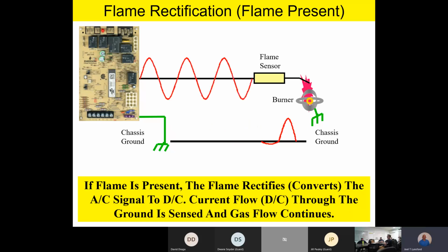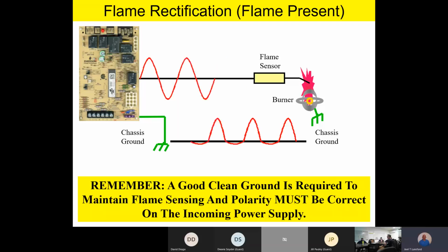Now it should be noted, if you take a look at this little graph, it's actually a pulsating DC along the ground plane. But this is why it's really super important that you have a really good, clean ground on your furnace. It has a good solid ground to earth ground, because it's part of your flame sensing circuitry. The polarity also has to be correct on the furnace. If you have reverse polarity between neutral and hot, it's not going to burn anything up, but the board will not be able to sense the flame if the polarity is backwards or if you have a poor ground.